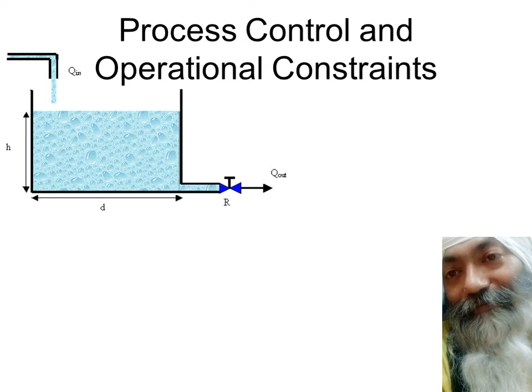As you can see, I'm revising. You can read it out. The buffer tank is to contain the mismatch of the flows. Inflow from the top is taken to be totally uncontrolled. Outflow is somewhat controllable. So one of the two has to be controllable. In this case, we have taken the output to be controllable. And if it is not controlled, it will result in wastage either by overflow or by drying out.